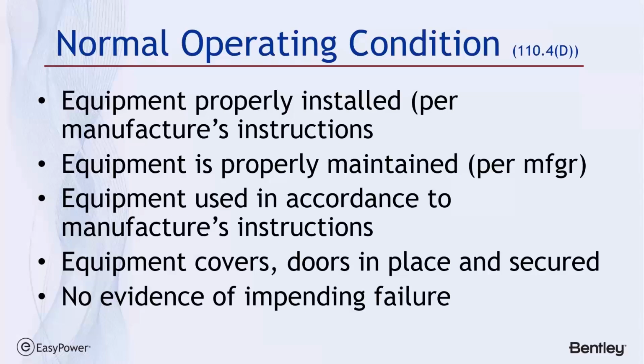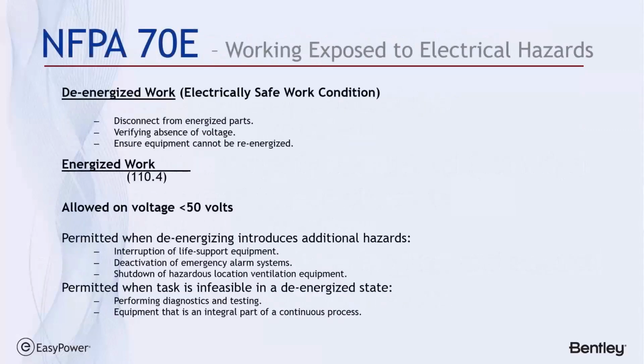The equipment must be properly installed per manufacturer's instructions. Equipment's properly maintained, used in accordance with manufacturer instructions. All the equipment covers are in place and secured, and there's no evidence of impending failure. Well, if one of those requirements for maintenance is to do an adjustment, diagnostic testing, or inspection of equipment while it's running, you can't very well do that when it's de-energized. So that's this last category of permitted hot work.